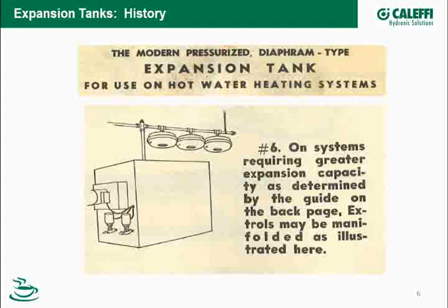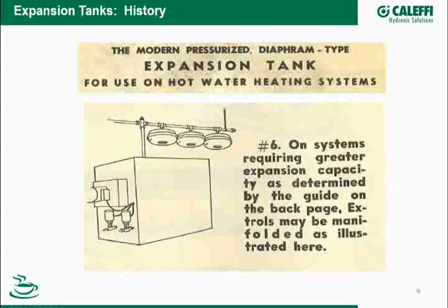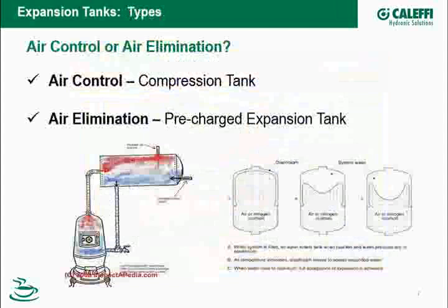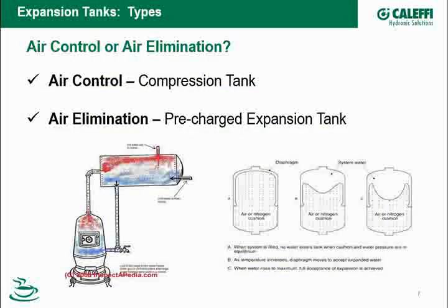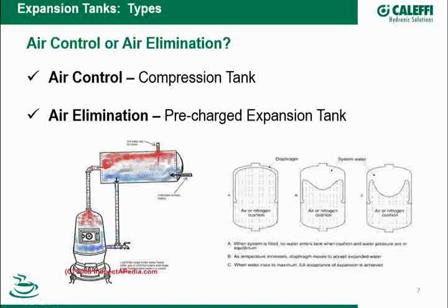Now, the question always comes up, expansion tank or compression tank? This is really a discussion of systems. Am I trying to do an air control system or am I trying to do an air elimination system? The compression tank is usually associated with something called air control. We'll get into the details in another slide, but it's a certain philosophy and design of a system. A pre-charged expansion tank is normally associated with air elimination. Let's first look at air control.